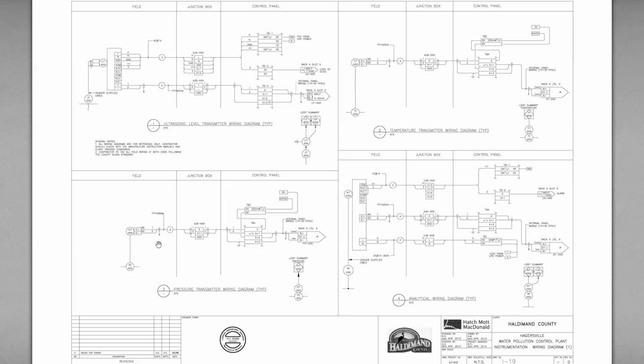Maybe not tell you every terminal on every single device, but this is a level transmitter here. The level transmitter receives power, so line, neutral, ground to these sections of the level transmitter, and the 4 to 20 comes back this way. This would be a 4-wire analog device. This would be a 2-wire analog device because it only has 2 wires coming back, and it's actually requiring loop power to be provided through it.